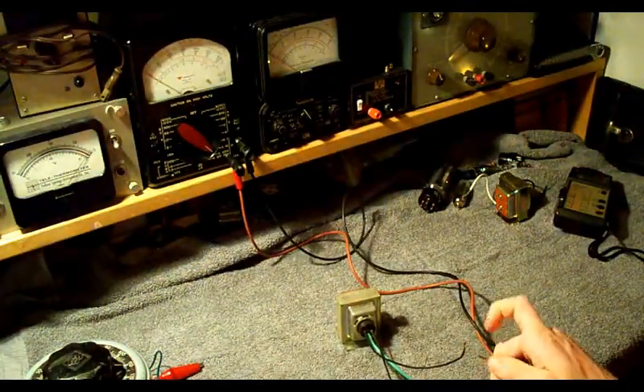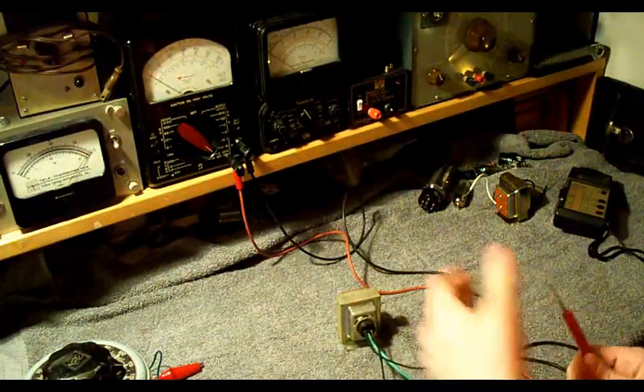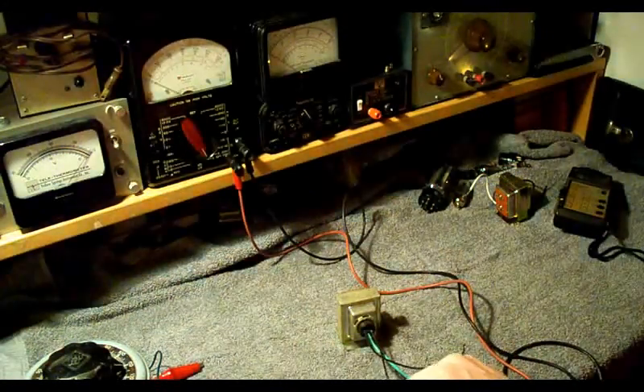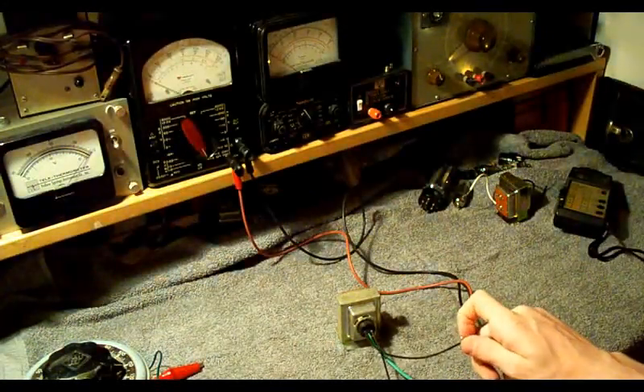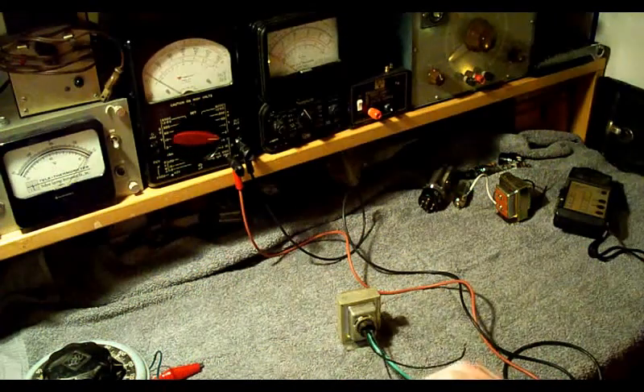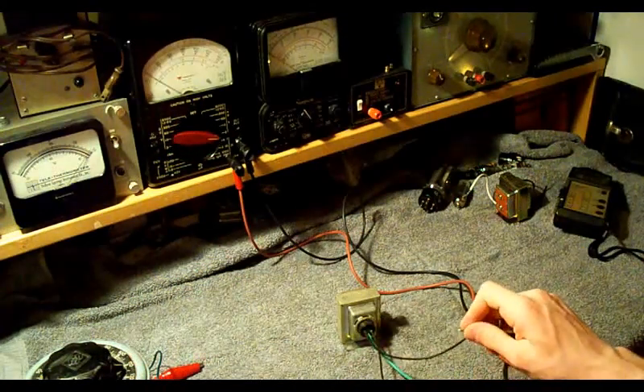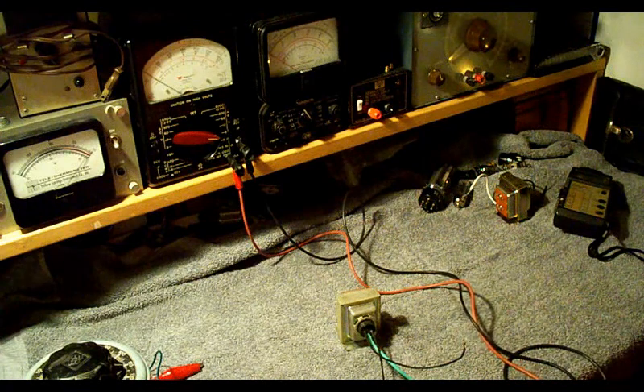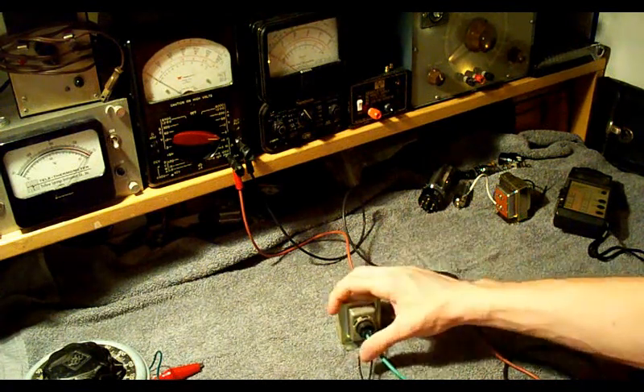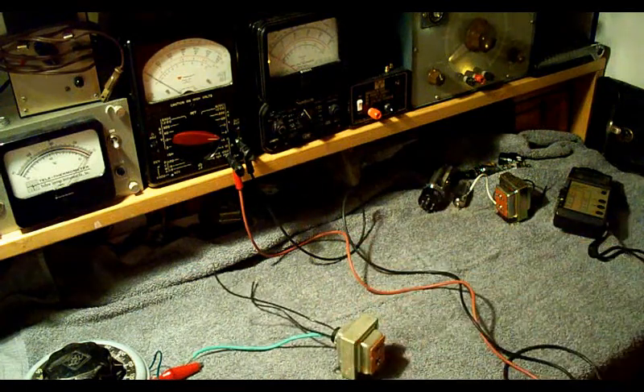Last time I got a reading here, I don't know. Well, it seems to me that something is already going amiss with this transformer. Again, times 1. Nothing. So right away, we can tell something is wrong with this transformer by the reading on the primary. So now we're going to check the secondary.